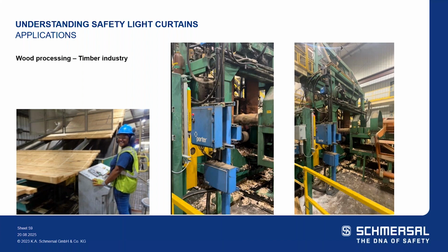And they were looking at a brand called Telco measuring light curtains that offered parallel and cross scanning beams to determine the location of the log and how many logs are going through. We got the order because we had the light curtains on the shelf. We could meet their installation time frame. Telco had a 2-month lead time, and they also realized that the light curtains were overkill for what they were trying to monitor. So they were simply able to utilize our standard light curtain and program in the blanking.